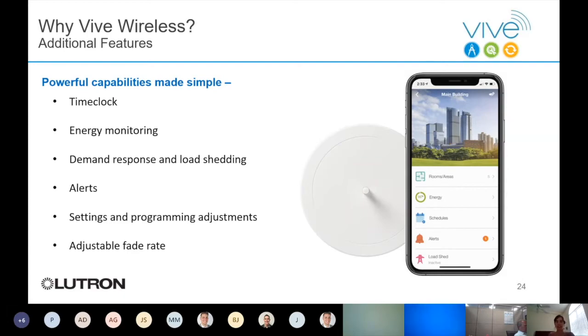One of them is a time clock, so you can schedule based around hours of the day or sunrise and sunset. It's an astronomical time clock, so it'll be consistent throughout the change of seasons. We just went through daylight savings, and it can adjust so that people never arrive to work or a facility in the dark. You could have these lights come on an hour or 15 minutes before sunrise, and it'll always adjust throughout the year.